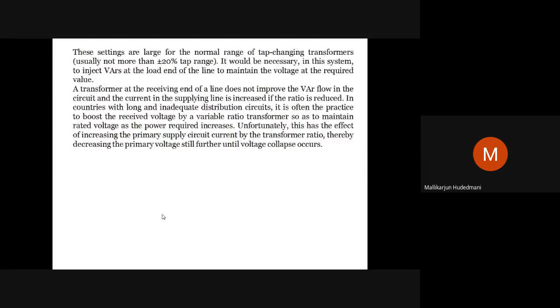Once I get Ts, given there is a design criteria, product of Ts into Tr must be 1. With this, what will I get? Ts, I know. Ts into Tr equal to 1. I just take inverse of this, that is 0.86. So Tr should be 86% of the tap, and Ts must be 1.16. So this is how you get tap settings at the sending end and tap settings at the receiving end.